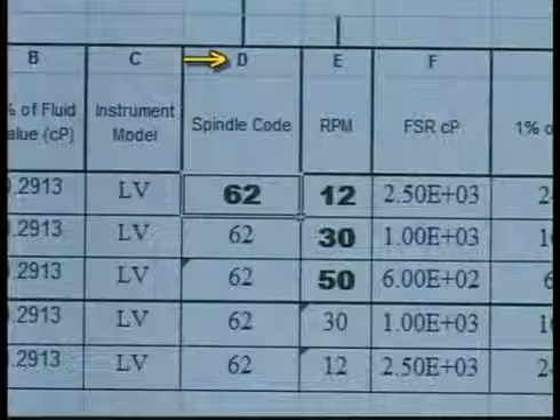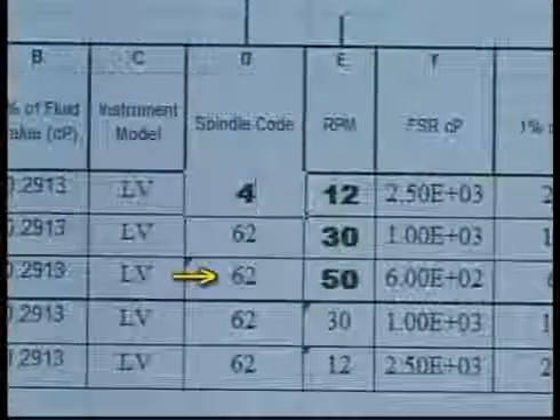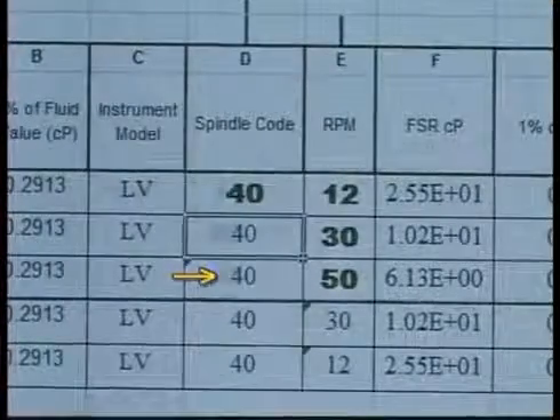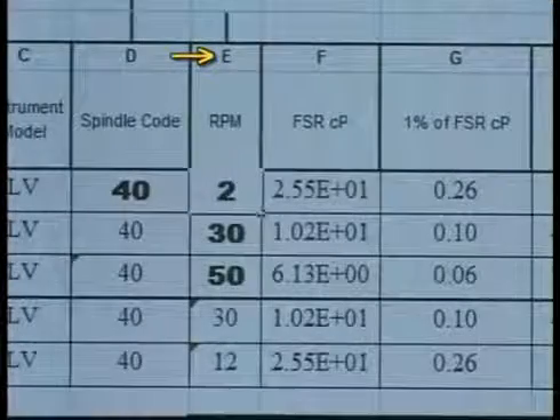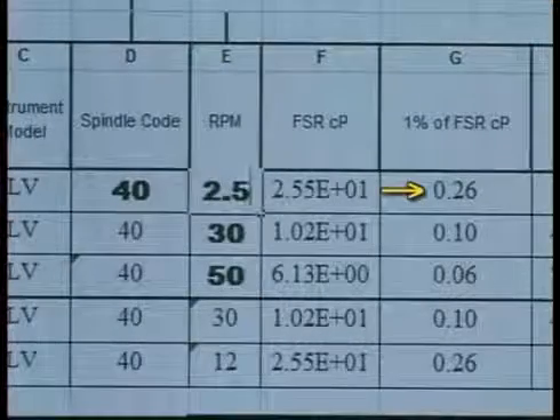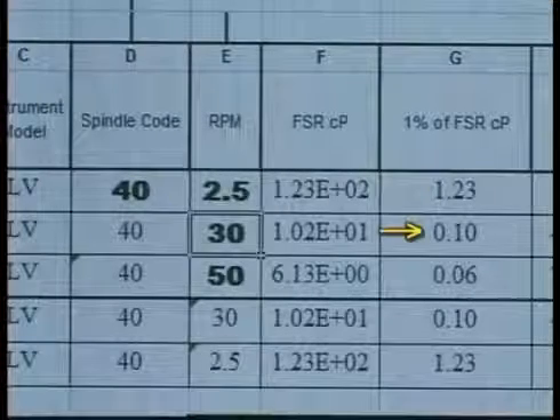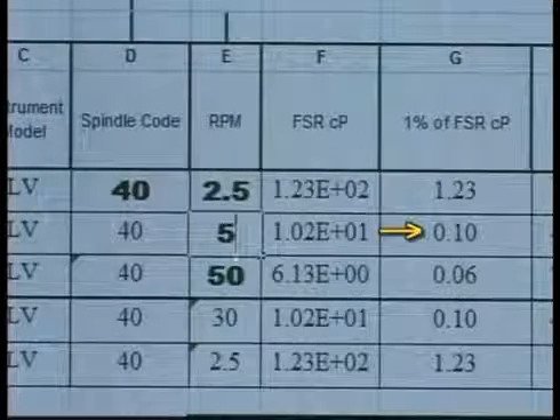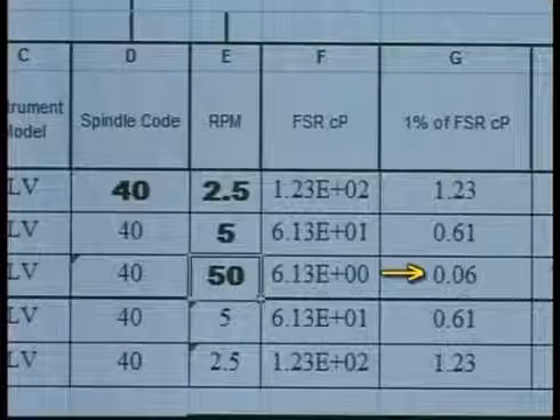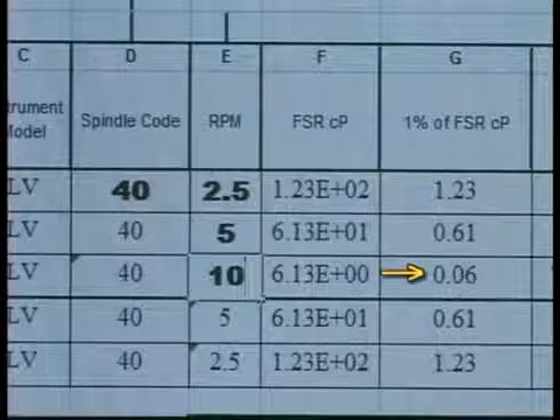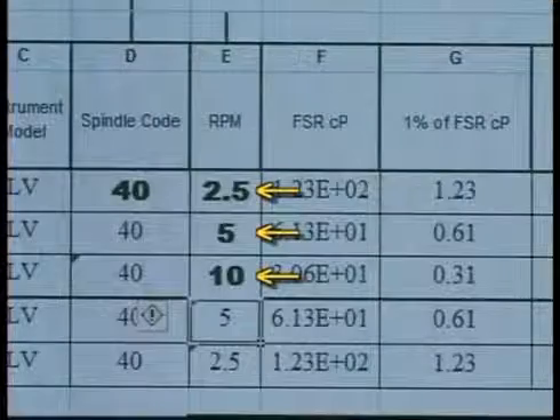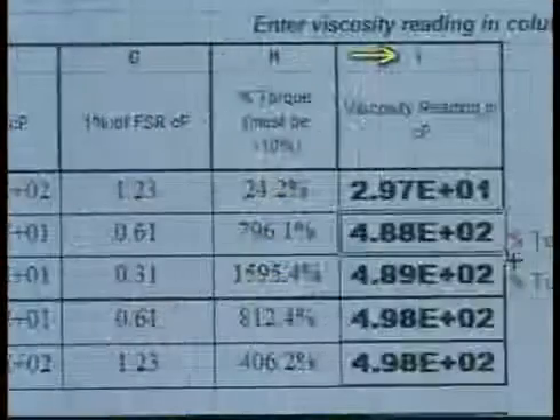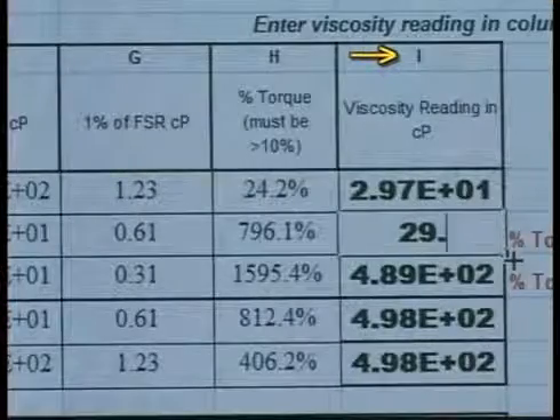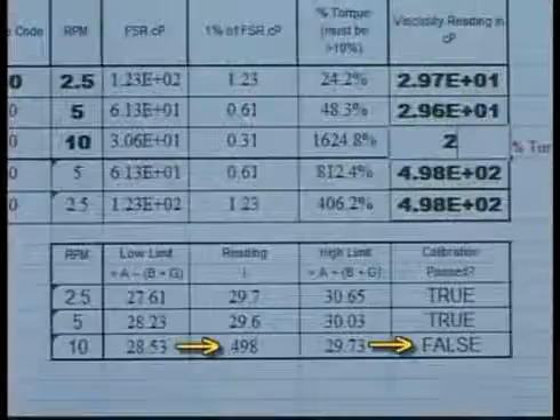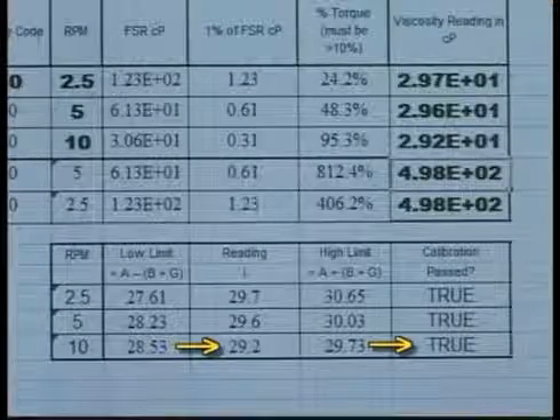Enter the spindle code in column D. Again, the fields in this column will automatically update. Enter the 3 speeds you will be running in column E and observe that the 1% full-scale range in column G is updated. This is the accuracy of the viscometer at this measurement range and rotational speed. Now, run the 3 speeds you have selected. Record and enter the data in column I. Your results will show up in the box below.